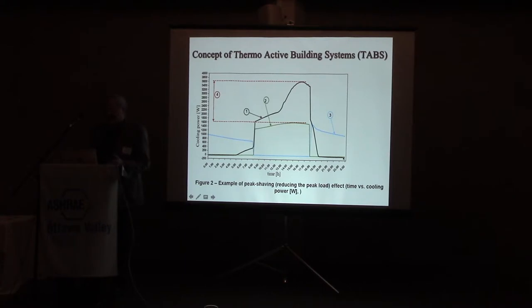So when we now have a hydronic system to remove some of this heat, the goal is that you should have a system that can remove the same heat as what was introduced for the internal loads from people and from external. So we basically have to remove the same as the area under this curve. And what is done is really by the combination of the two systems. We need a ventilation system for indoor air quality, but here we can do some of the cooling. So during daytime, we are running the cooling on the air system, so we may remove some of the heat here. But you see, this area is smaller than the whole area, so we're not removing all of it.